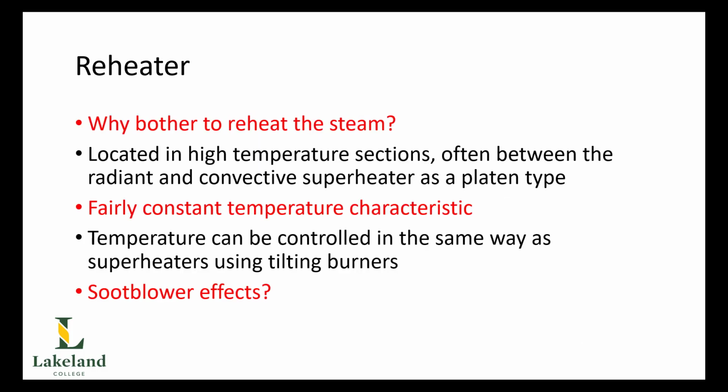Okay, so there's a few questions then that we need to summarize up with and also take a look at the characteristic of the reheater regarding its steam temperature. So first of all, why would we bother to reheat the steam? Well, the answer is the same as why we would bother to superheat the steam. That is, we want to get as much enthalpy as we can out of the steam, which means we want to put it up to the highest pressure and temperature that we can. Now we can get more work out of the turbine and greater efficiencies.